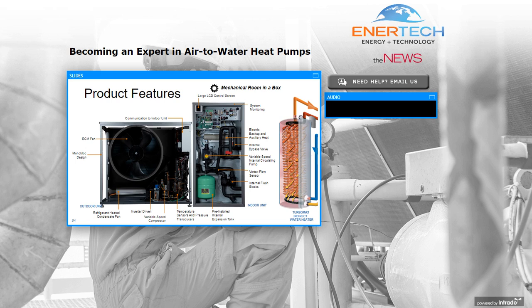So if you're looking on the left-hand side, that's the outdoor unit with the covers removed. You see here the vapor injection variable speed scroll compressor, as well as where the refrigeration circuit is. There's a refrigerant heated condensate pan, so that any condensate that's coming off of the coil is not going to freeze before it exits the unit. The ECM fan, of course, keeps the system very efficient and extremely quiet. You can barely hear this unit run.